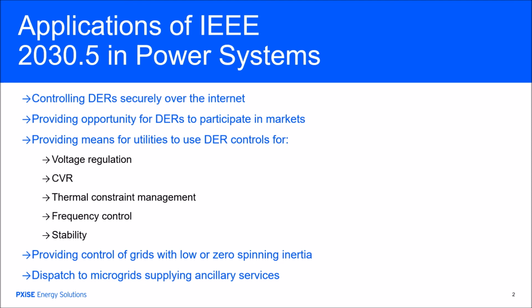Additionally, if you have the ability to read data from the DERs, this provides an opportunity for utilities to offer more direct control of the distribution system. In particular, voltage regulation is possible. In fact, autonomous voltage regulation is supported by the standard. Conservation voltage reduction technology can also be applied.